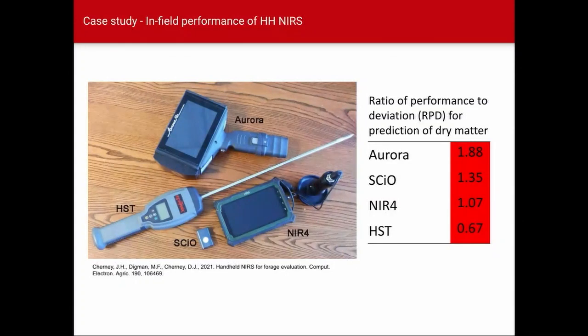We look at the RPD for moisture, which I would say should be the low-hanging fruit for these types of devices. There should be two moisture absorbance bands in that 950 to 1650 nanometer range. We'd have one around 970 nanometers and one around 1440, so we should be well represented. The SciO device would only capture one of those bands, so that could explain lack of efficacy there, but if you look at our chart here, the SciO device didn't do that poorly relative to the other devices. All of them wouldn't meet our standard that we've set up for RPD.